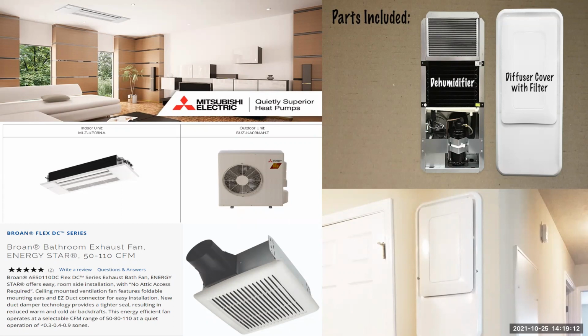The last thing you see is the Broan bathroom exhaust fan. Typically we try to stay away from an exhaust-only ventilation strategy in these tighter buildings, but because we're using dehumidification and inverter heat pumps, it allowed us to feel comfortable using an exhaust-only strategy. We could use the bath fan to double as the ventilation equipment, so it was a win-win. We didn't need a separate piece of equipment for ventilation, and it went right out the wall in the bathrooms since they're all on exterior walls.